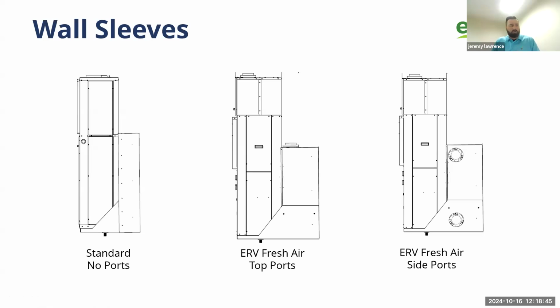So often in a service situation, one of the first things we train our contractors to do is take a quick walk around the building. You'll see some pictures of what the louvers look like, but you can see if there's a drain plug from outside the building, just from water that could be trickling down. And those are always the ones you want to catch ahead of time. So the wall sleeves come for the fresh pack.